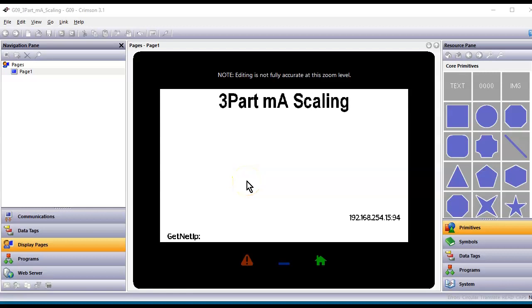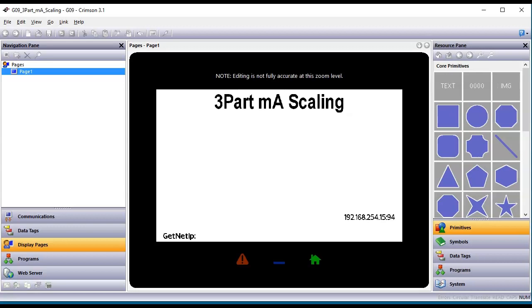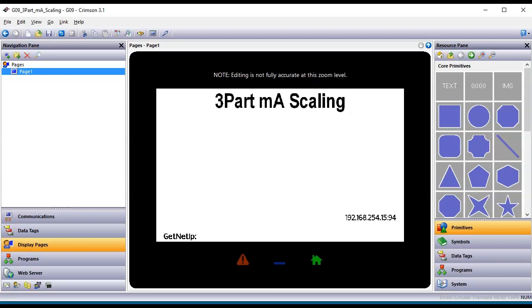Hello there folks. This example is going to be a little bit on scaling. I've done a number of videos on scaling but this one's going to be a little bit different. We've got an application where a customer has a 4 to 20 milliamp sensor and they're telling me the sensor will go between 0 to 3,000 psi over that range. However, they'd like to enter a number at 12 milliamps that is not exactly 1,500 — maybe they need to do some calibration. I call this a three-part milliamp scaling: you have the value at 4 milliamps, a value at the halfway point, and a value at 20 milliamps.